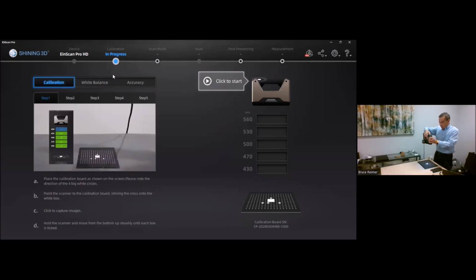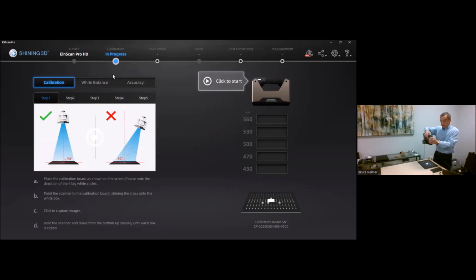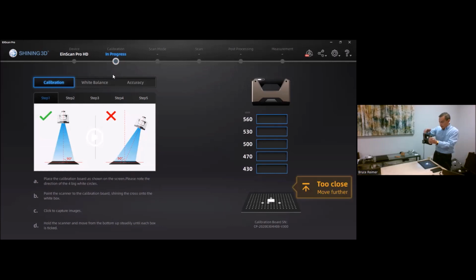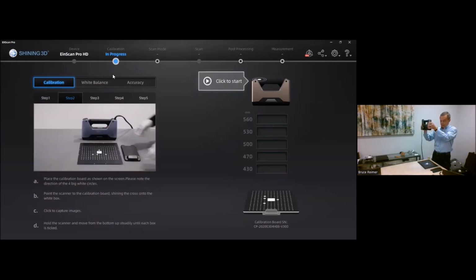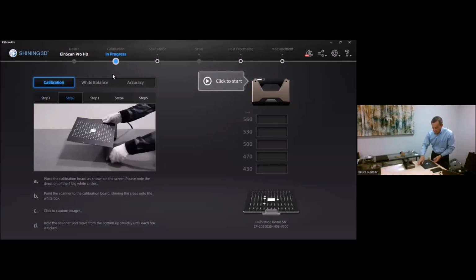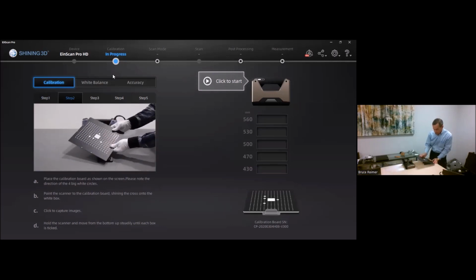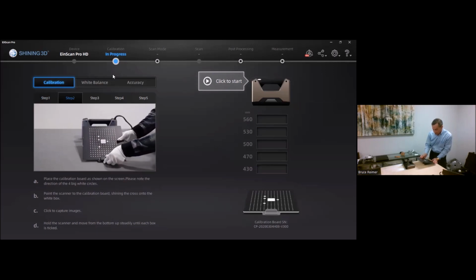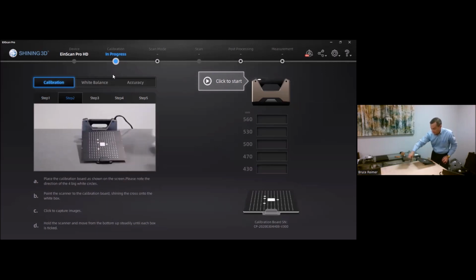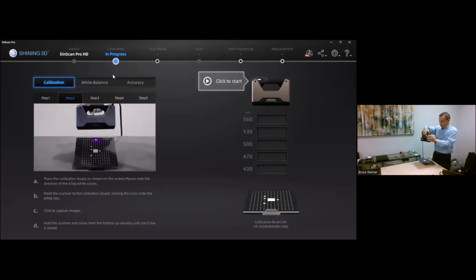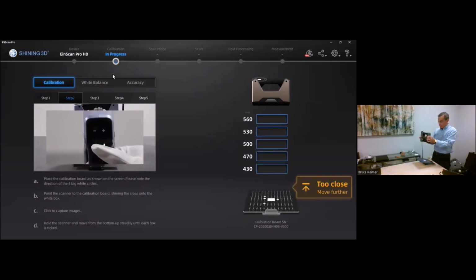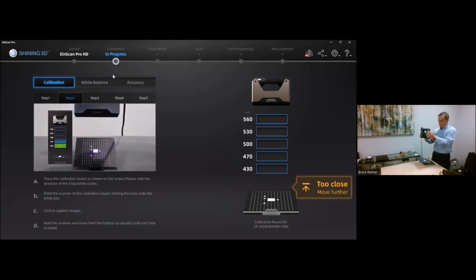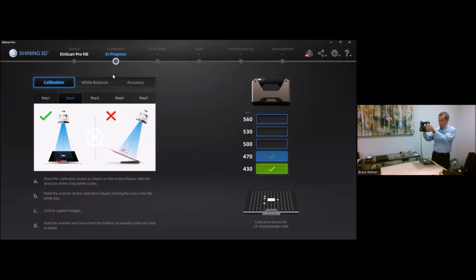Grab the scanner. We hold it vertically with the crosshairs focused at the center of the board. We press the scan button, and then we just simply raise the scanner vertically slowly. And as you do so, you'll see that the software is giving check marks in each one of those boxes. Then it immediately takes you to the next step, which uses the calibration stand. We position the primary dots on the calibration board as shown, orient the scanner, hit the scan button, and raise slowly while keeping the crosshairs focused on the center.